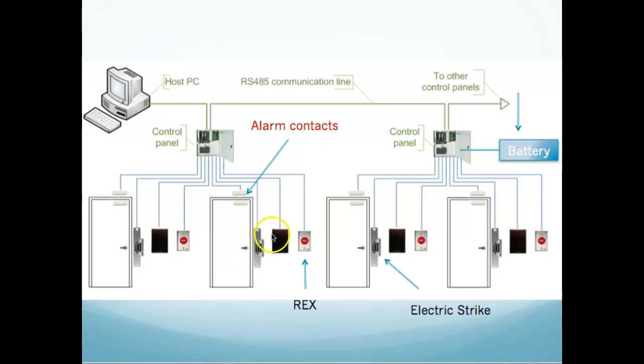Now, one of the things that's kind of unique is that if you use the reader to get in, the reader signal and the door separation are coming in just about the same time. First you use the reader, and then you open the door. When you use the reader, it goes up and says, a reader is being used to open the door, and Brian is allowed in here. So when this alarm comes in, ignore it and don't report it to the host. It's called shunting the alarm. So when you use a legal entry to come into a door, the alarm won't come in.